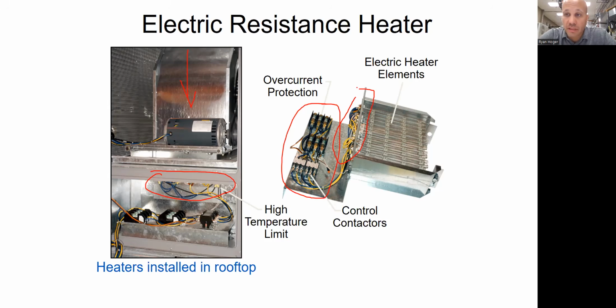So now their choices are heating it with electric, which is 100% efficient, or heating it with a heat pump, which is a couple hundred percent efficient. You should definitely get the heat pump. And you'll still have electric heater as well, because we need that auxiliary heat sometimes.